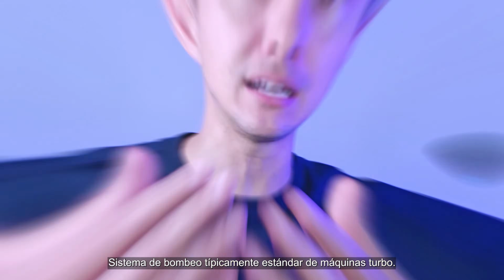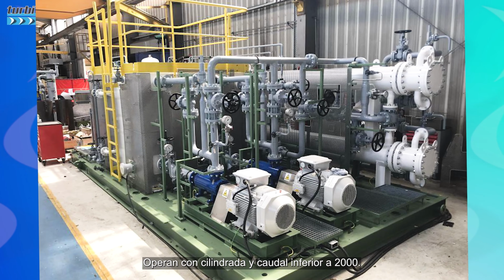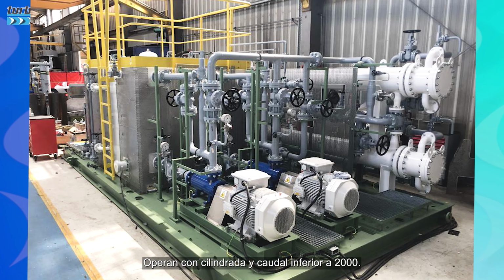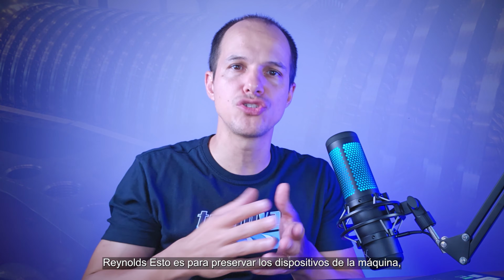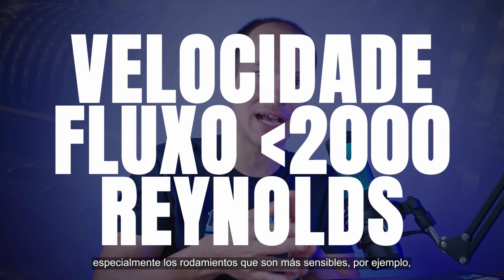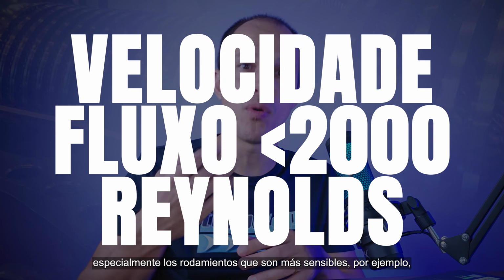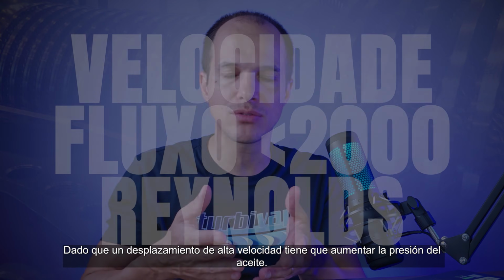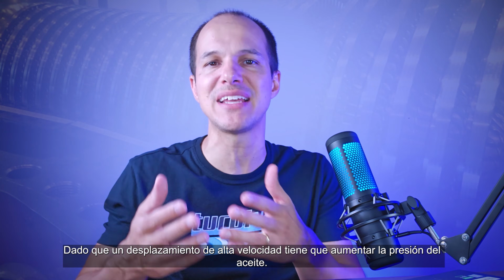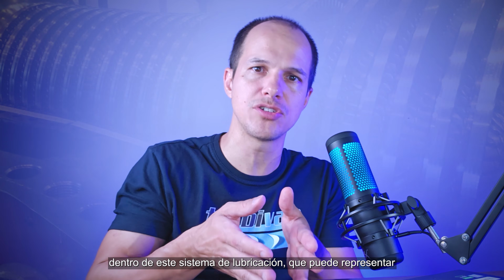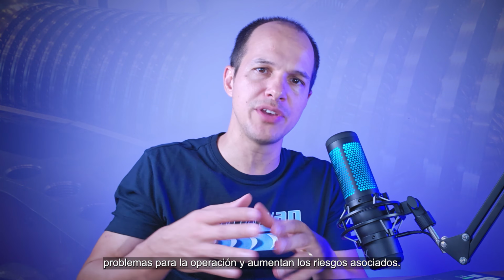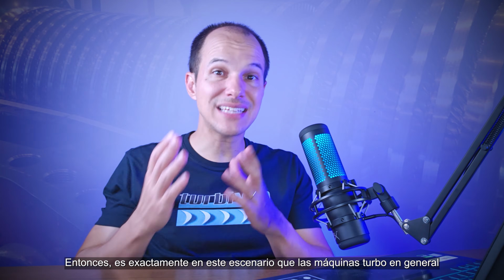On the other hand, high-speed flow is considered the most effective. Typically, the standard pumping systems of turbo machines operate with displacement and flow below 2,000 Reynolds. That's to preserve the machine's devices, mainly the bearings, which are more sensitive, for example. Since a high-speed displacement has to increase the oil pressure inside this lubrication system, it can represent problems for the operation and increase the associated risks.